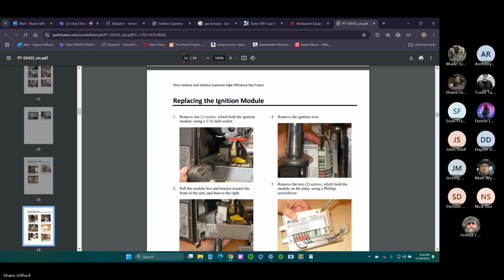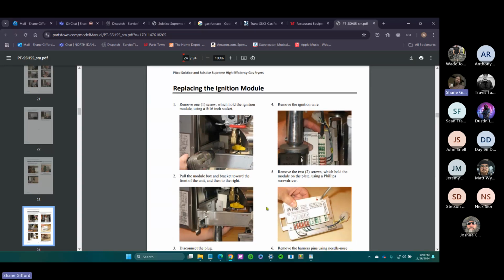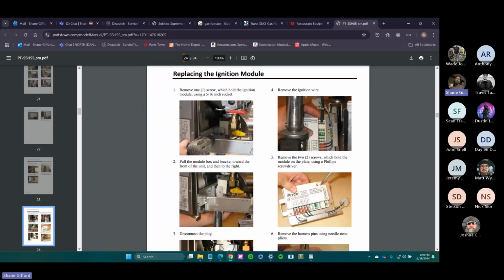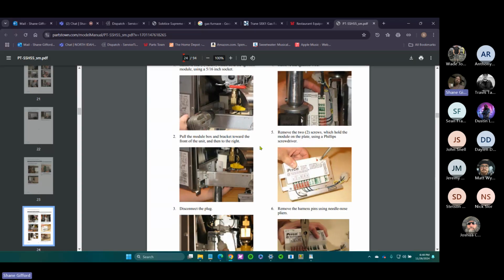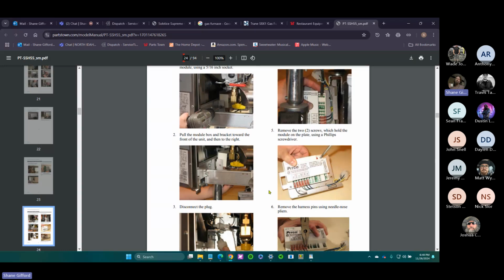Here you go. The ignition module on Pitcos is usually in this location, or I've seen them zip tied and hanging on weird stuff. Someone up here actually thought it would be a good idea to take this ignition module, which is made out of plastic, and screw it to the plate right in front of the heat exchanger. Where he mounted it was super hot and it melted the board. So you don't want to do anything like that. Be cognizant of where you install this and where you put it.